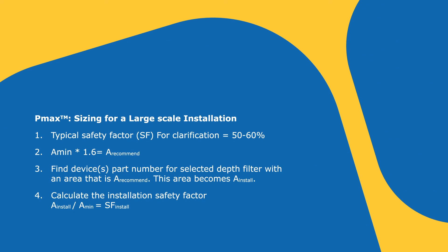So then what do you do with a min? Now you need to size for your large scale installation. We typically include a safety factor for clarification is between 50 to 60%. So what you would do is you would take the a min number, you would multiply that by 1.6 and we could call this a recommend. And then you would use, you could call customer service or a process development scientist, your account manager, a catalog or a website for Millipore, EMD Millipore. And you can find the device part number for the selected depth filter area with an area that would be greater than or equal to a recommend. And this area could become your a install.